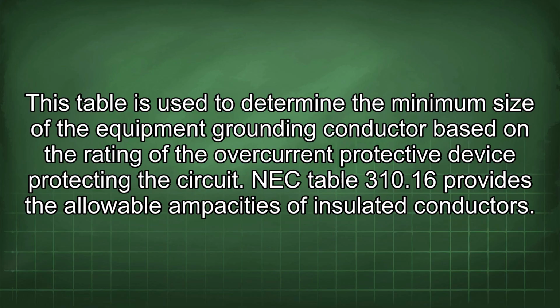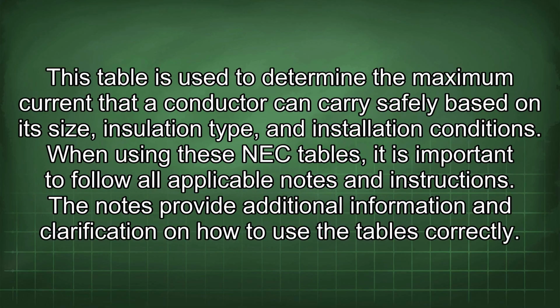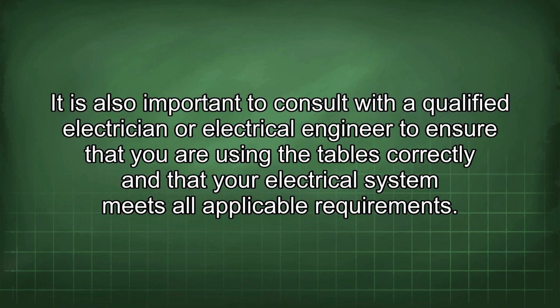NEC Table 310.16 provides the allowable ampacities of insulated conductors. This table is used to determine the maximum current that a conductor can carry safely based on its size, insulation type, and installation conditions. When using these NEC tables, it is important to follow all applicable notes and instructions. The notes provide additional information and clarification on how to use the tables correctly. It is also important to consult with a qualified electrician or electrical engineer to ensure that you are using the tables correctly and that your electrical system meets all applicable requirements.